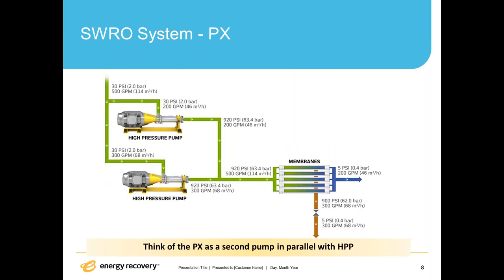You can think of the PX as a second pump in parallel, where the PX handles 300 gallons a minute of the total 500 gallons a minute and pressurizes it to the full 920 PSI. The two streams out of each pump then join together and go through the membrane system.